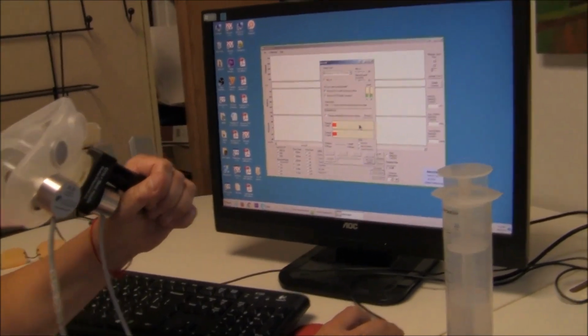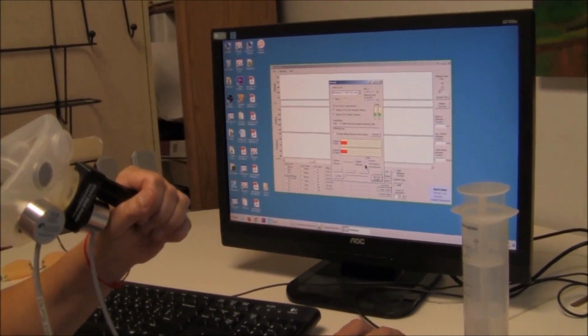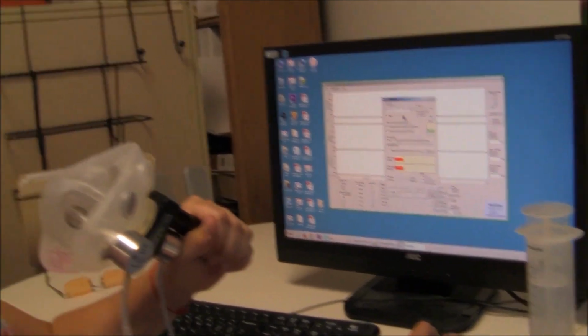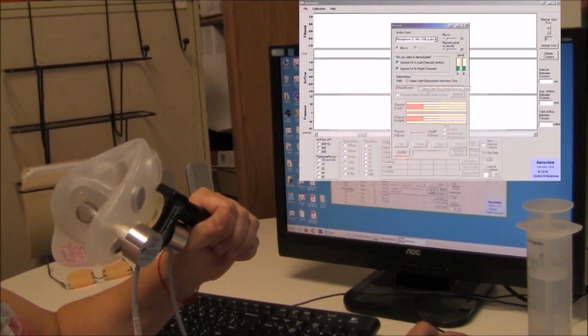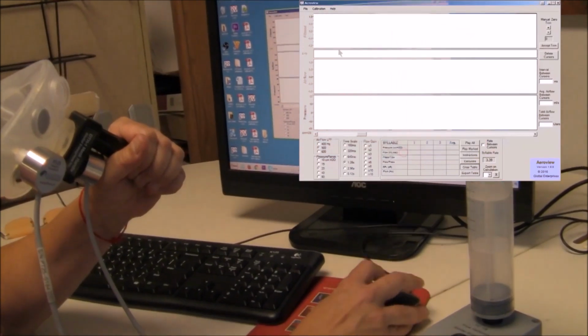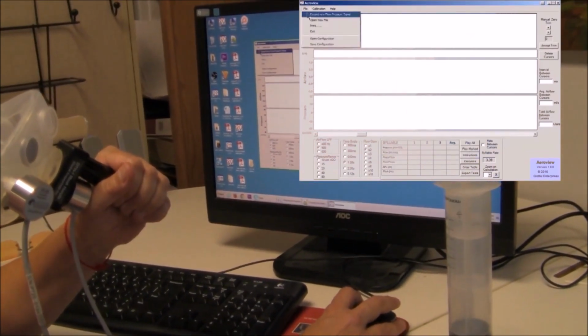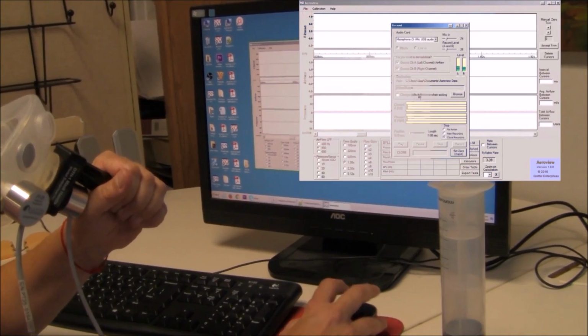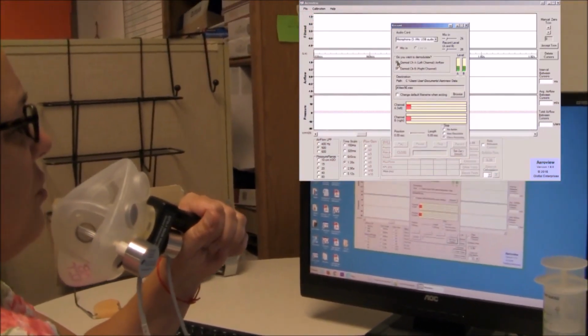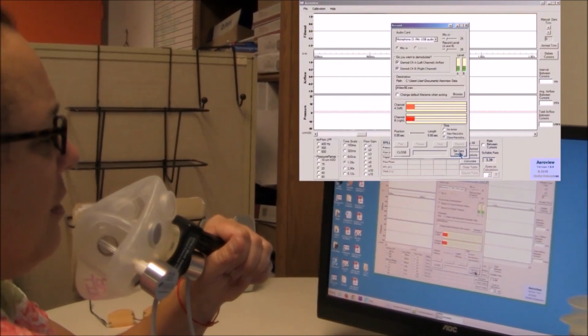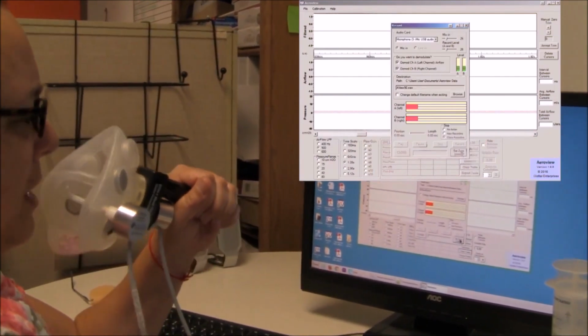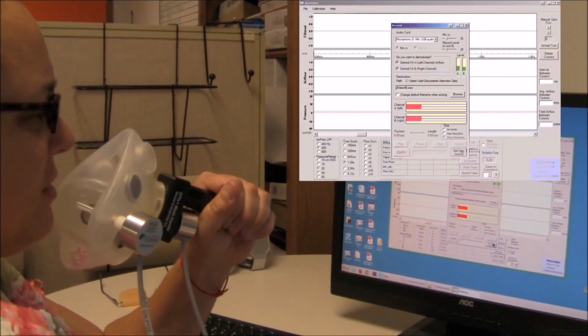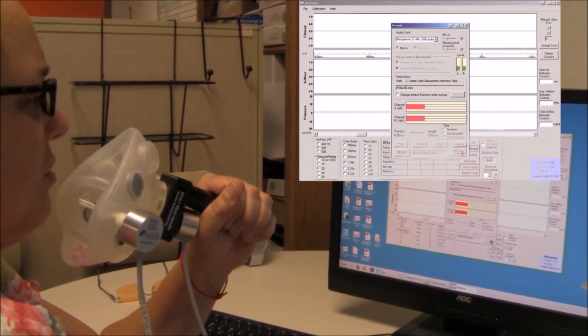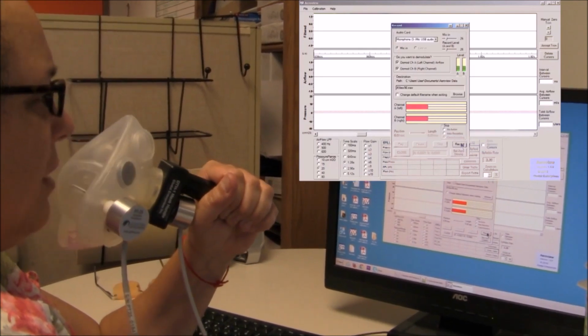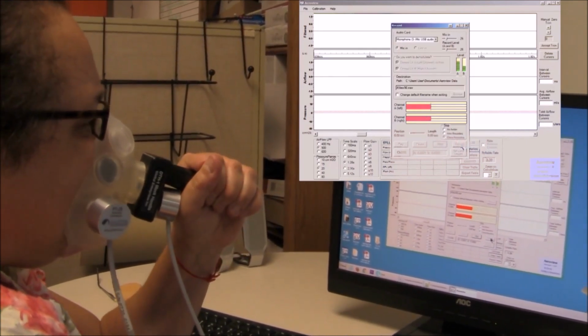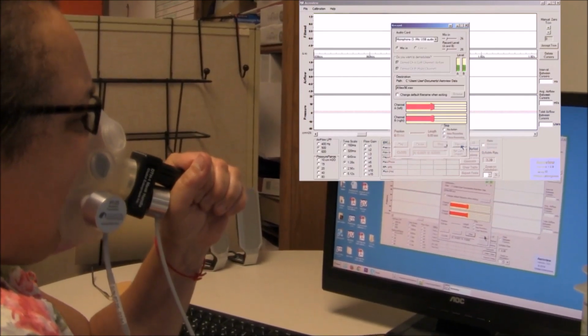Okay, I'm going to now record a pressure and flow signal. So I've pressed File, Record, New Pressure Flow Signal. And now I want to make sure my demodulation is clicked. I press Set 0. And make sure when you press Set 0 that your mask is right up to your face. So you press Set 0. And then I'm going to record. Bap, bap, bap, bap, bap, bap, bap.